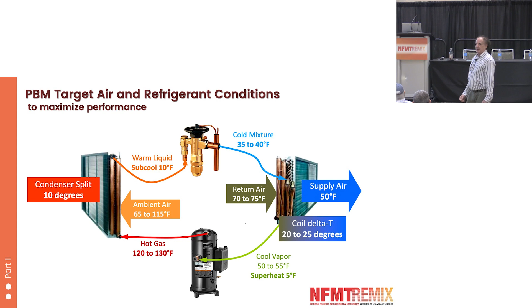And then supply air, coil delta T is another good indicator there, especially in this part of the country where it's humid. You want a good solid 20 degrees on your coil. And I know that technicians usually, if there's 15 or 20, they say, hey, it's working. And it's true, at 15 degrees, it'll still provide cooling, but it won't provide much dehumidification. And it does indicate that somewhere in the system, something's not optimal. Okay, the case study.